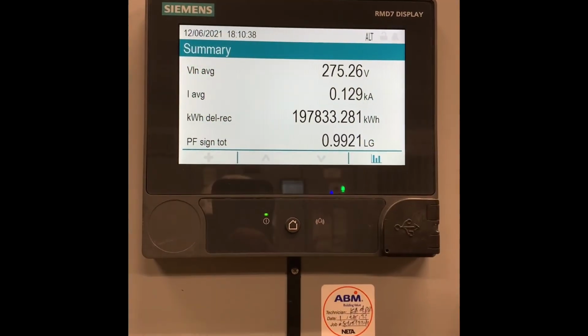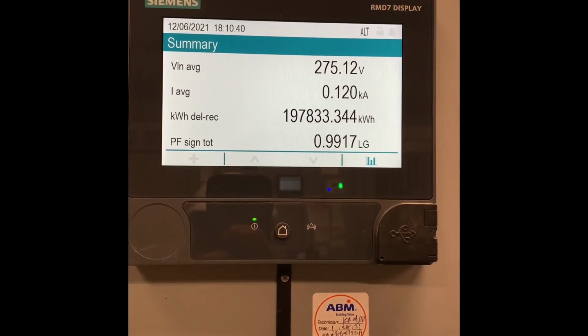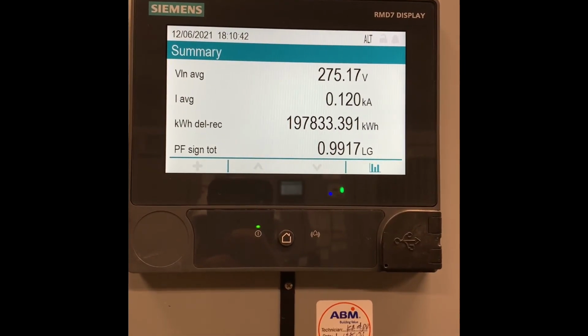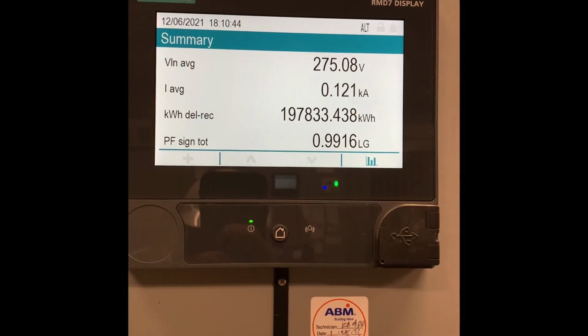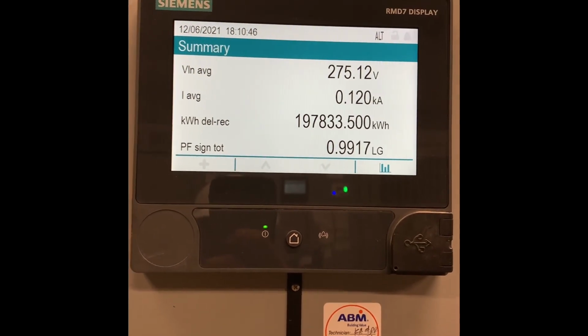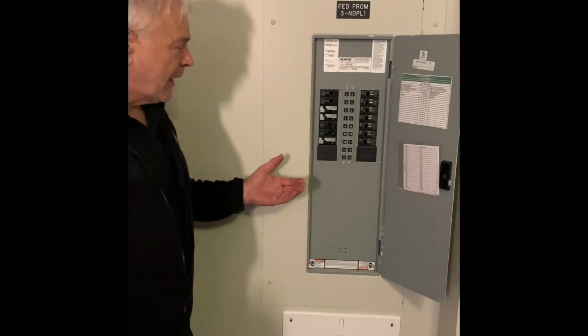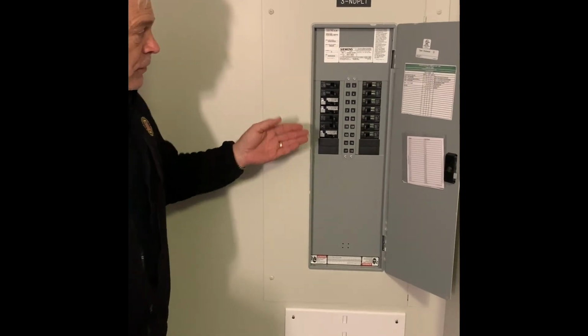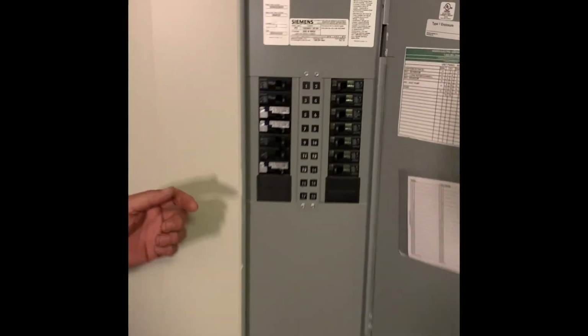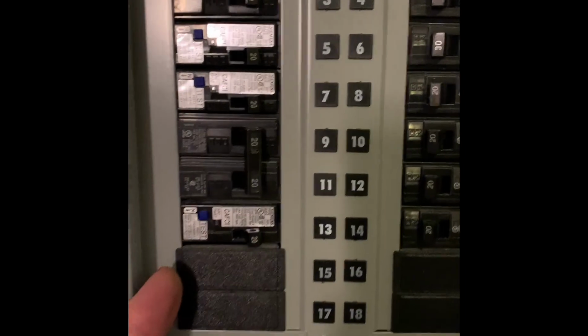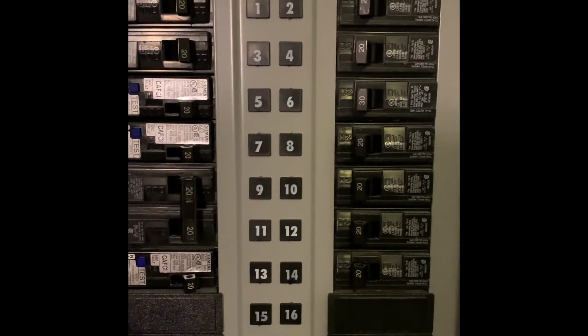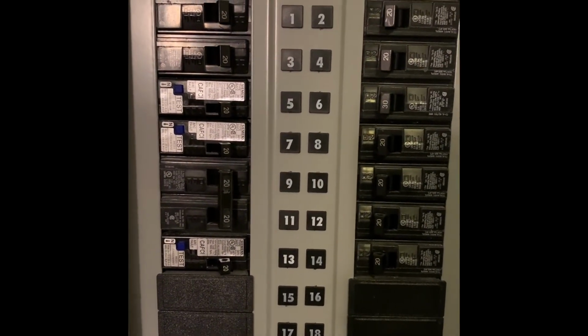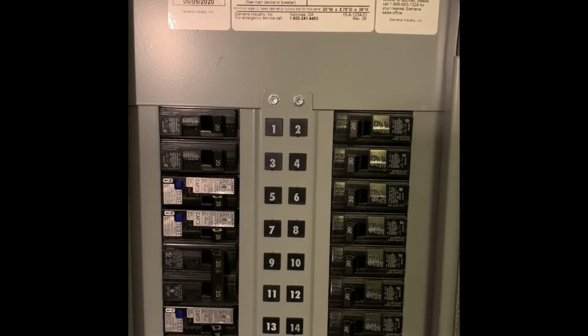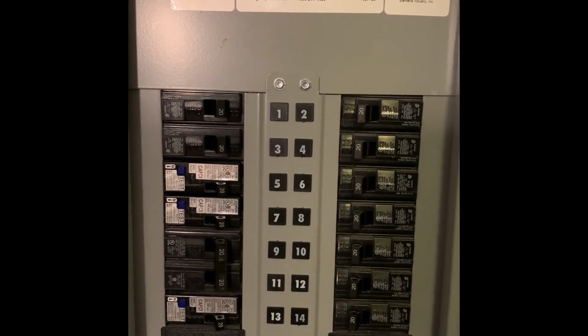Digital meter, you ready? Yep. Again, a digital meter with functions. All of the functions and the parameters are clearly identified in the O&M manuals. Okay, now we're in front of one of the unit panels. This panel is very similar to the breakers that we already showed down there. Same thing, on, off, and in the center is tripped. Again, if you find something that's tripped, identify why it is tripped before you reset it.